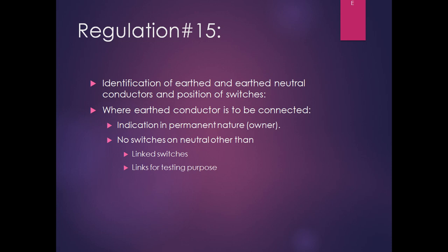The basic idea is that if you put a switch on the neutral conductor for a single phase system and switch it off, the load will go off. However, the phase will still be extended to the equipment. If somebody touches the equipment, he may be electrocuted. That's why switches shall always be provided on the line side or phase side, not on the neutral side. You can provide a switch on the neutral side provided it is linked with the switch on the phase side. That means a DP switch or TPN switch. Other than that, you can also provide a link in the neutral.